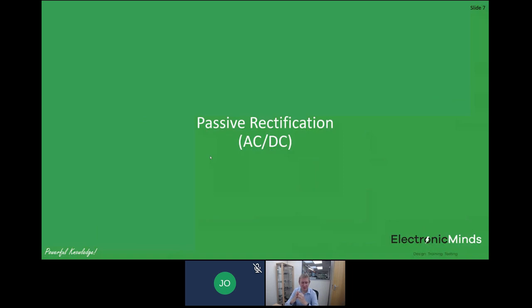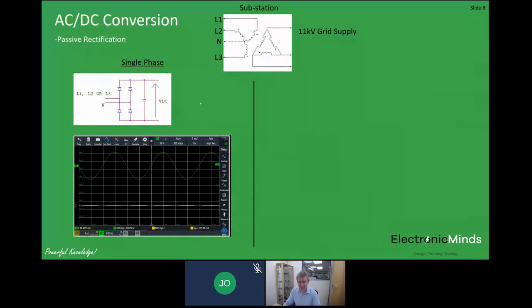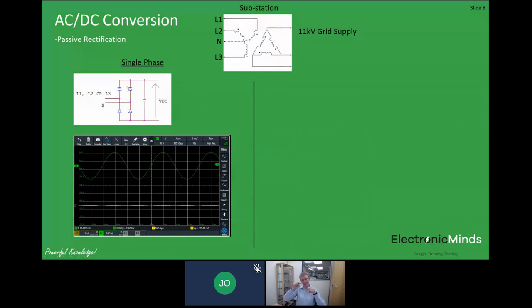I mentioned passive rectification at the start of this webinar, and this is very commonly used. On a single-phase system it's about the most basic thing you can imagine: a bridge rectifier feeding a bulk capacitor. As the mains moves up and down, the capacitor recaptures the DC content of the waveform once it's been peak rectified. The output of this bridge rectifier looks like a full-wave rectified sinusoid — bipolar in, unipolar full-wave rectified out — and the capacitor smooths that to recapture a DC level.